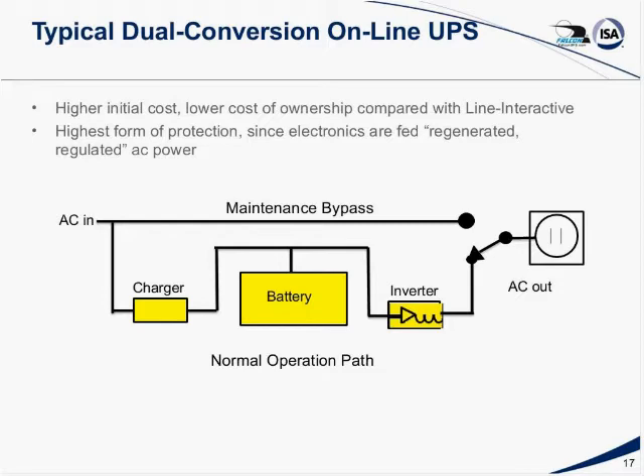Okay, Larry, before we go forward, Mike, is there anything you'd like to add about online UPS? Yeah. The main thing to remember with the offline and the line interactive is that the power goes straight through. The only surge protection, and Larry touched upon this, is a metal oxide varistor, which is the same device in the plug strip.